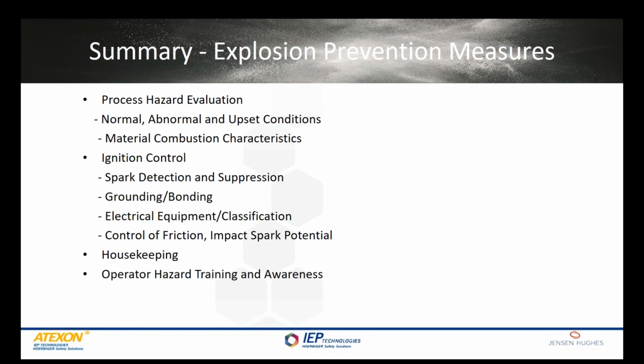Have the operators been trained to understand what the risks are of combustible dust explosion, to make sure that they're not doing hot work on vessels that are not being cleaned out? Just as a side note, I was at the aftermath of an explosion in which a dust collector had been shut down. Hot work was being done on the dust collector, but the pulse jets had not been turned off. And when the dust being liberated from the pulse jets inside the dust collector reached that hot spot, it caused an explosion with 2 fatalities. So proper training for the operators and for the maintenance people is an absolutely vital part of an overall explosion protection strategy.